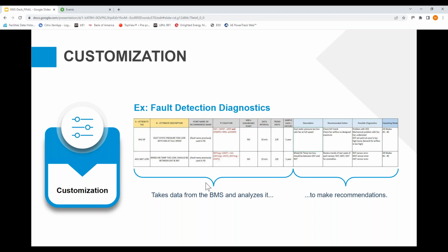In this case, it's probably most likely a sensor error. It could be broken, or maybe it's not calibrated anymore. And if you go and look at that trend data prior to going out to the field, you might even be able to tell which sensor is actually bad.